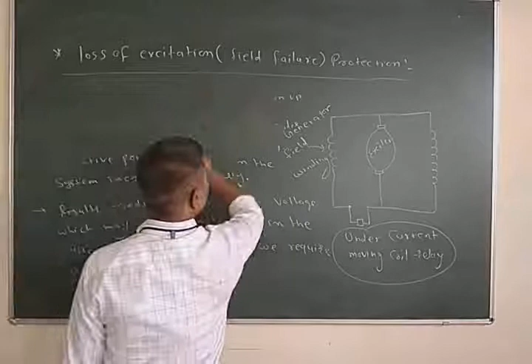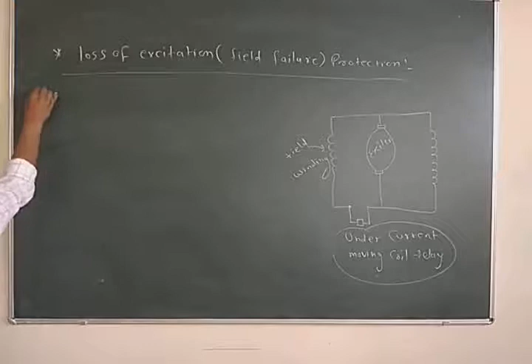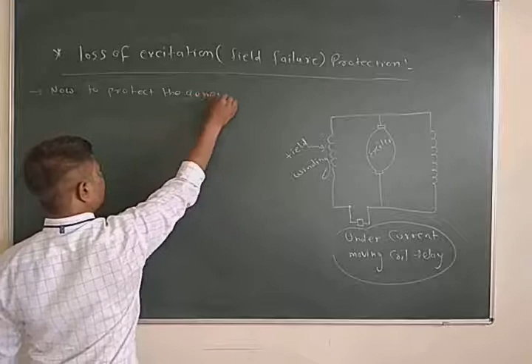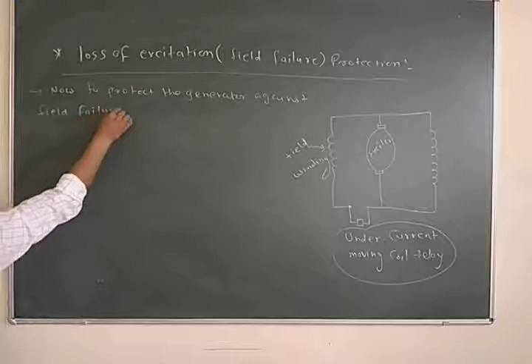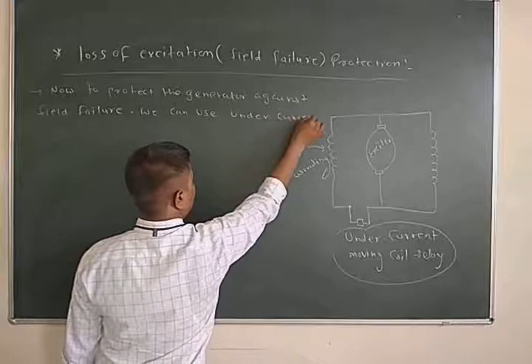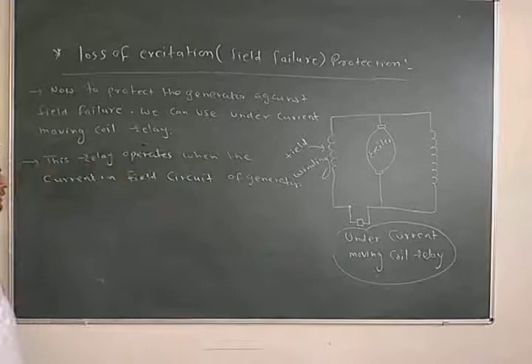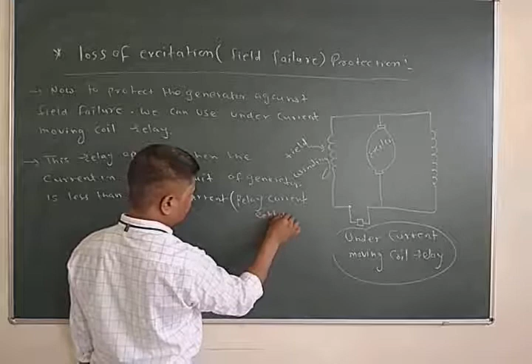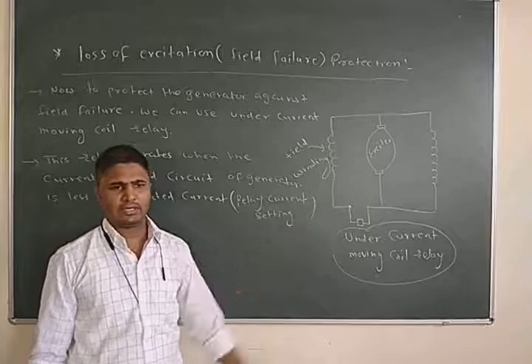Now, to protect the generator against excitation failure, against field failure, we can use an undercurrent moving coil relay. This relay operates when the current in the field circuit of the generator is less than the relay current setting or rated current. In this condition, the undercurrent moving coil relay operates and sends a signal to the circuit breaker, and the circuit breaker removes the terminals of the generator from the system, or isolates the generator from the rest of the system. This is the first method with the help of which we can protect the generator against field failure.